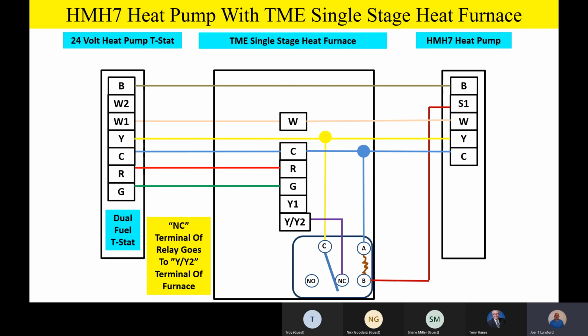That's going to be our high speed or high airflow point. And then our normally open will go up to Y1. Now, please notice something, team. On the TME furnace, even though it's a single stage heating furnace, I didn't know if you do this or not, but the TME single stage heating furnace actually has 2 stages of cooling capability. So that's why we have that Y/Y2 and a Y1 point on the terminal board, so you can actually select off the control board a low speed airflow and high speed airflow.